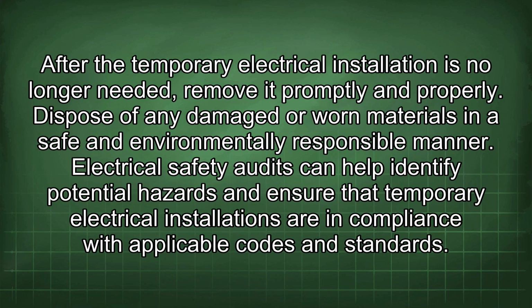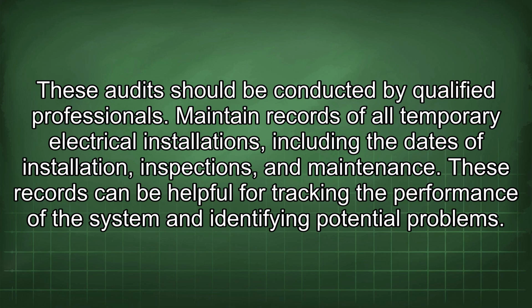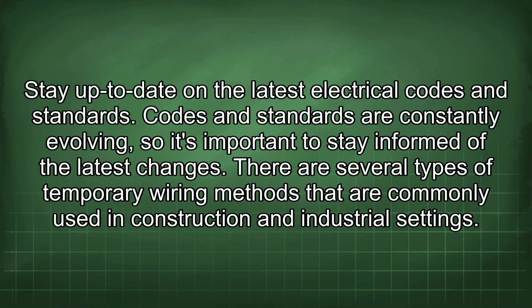After the temporary electrical installation is no longer needed, remove it promptly and properly. Dispose of any damaged or worn materials in a safe and environmentally responsible manner. Electrical safety audits can help identify potential hazards and ensure that temporary electrical installations are in compliance with applicable codes and standards. These audits should be conducted by qualified professionals. Maintain records of all temporary electrical installations, including the dates of installation, inspections, and maintenance. These records can be helpful for tracking the performance of the system and identifying potential problems. Stay up to date on the latest electrical codes and standards. Codes and standards are constantly evolving, so it's important to stay informed of the latest changes.